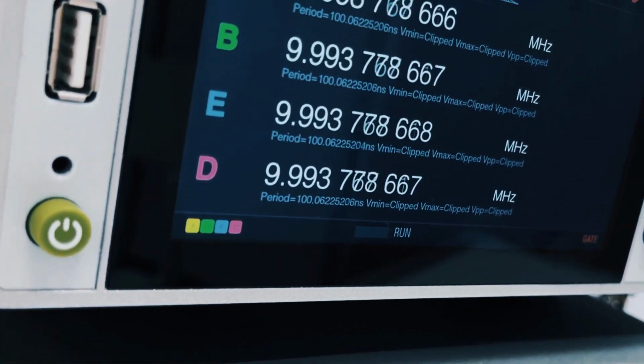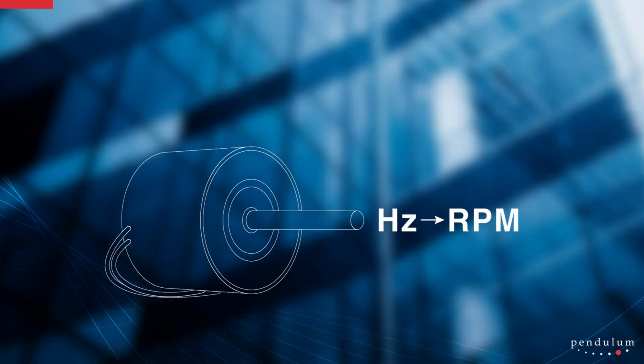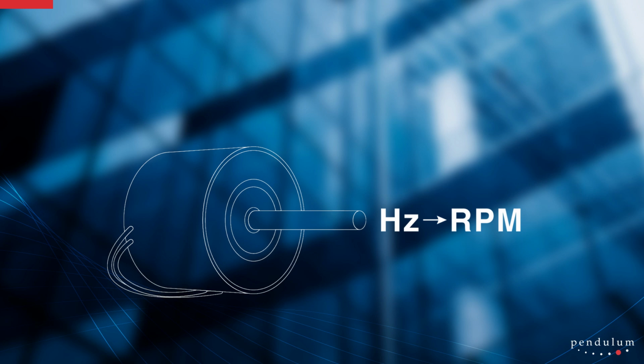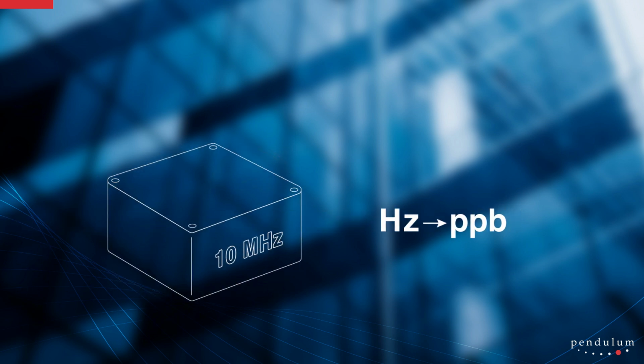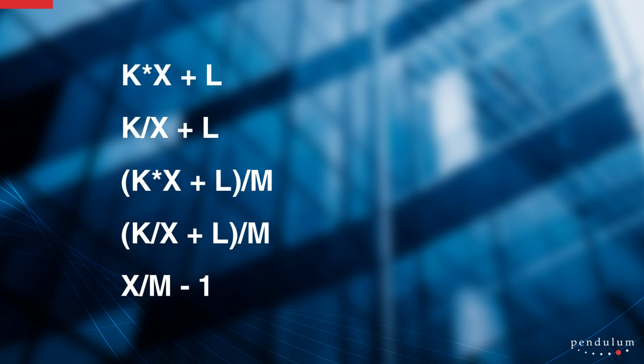obtain the required values. Typical examples include using a frequency measurement in Hertz to derive the revolutions per minute, RPM, of a rotational device, or measuring an oscillator's frequency offset where the result needs to be expressed in a ratio, such as parts per million, ppm, or parts per billion, ppb. This video demonstrates how simple arithmetic formulas can be configured on the CNT-100 series to obtain the necessary results automatically.